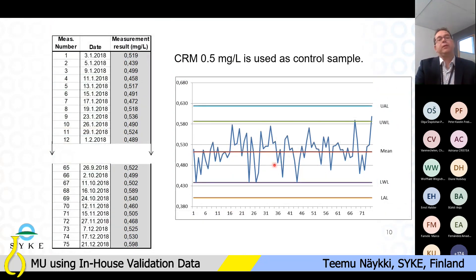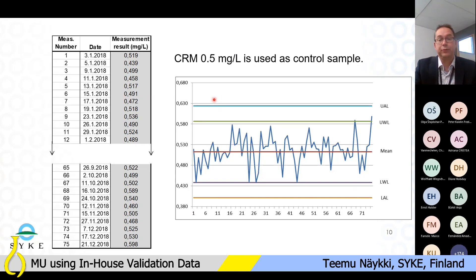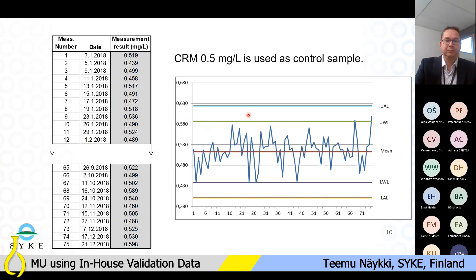The next step is to quantify the within-lab reproducibility using the same stable control sample that is measured over several days by different analysts, different calibrations, and different reagent batches at your laboratory. In this example, a CRM certified reference material was used as a control sample, and 75 measurement results were collected during one year from the control X chart of the laboratory. The results are entered into the MUkit software, which calculates the standard deviation, average concentration, and number of results.